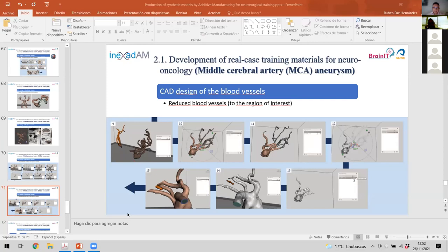Regarding the neurosurgical trainers, they gave us recommendations to improve the synthetic models. For example, they wanted the duramater to be made with a harder material, which is very easy — we can use another silicone or change the composition. But ultimately we need feedback from the neurosurgeons because they are the ones who really know the behavior of the material. That was one of the main recommendations and the easiest to apply.